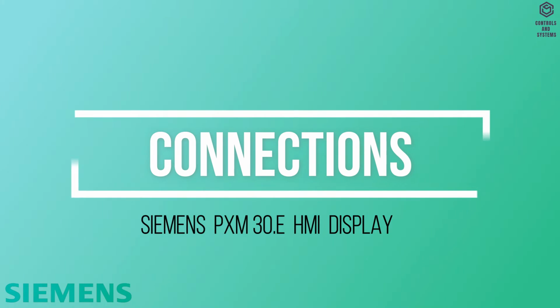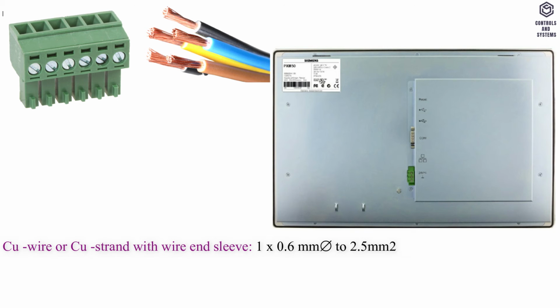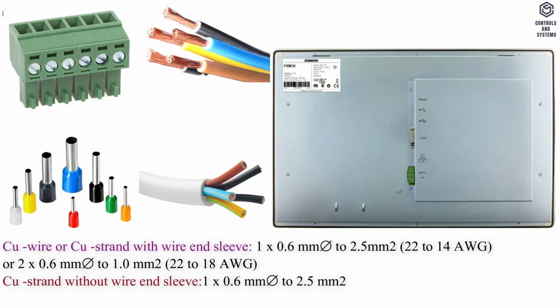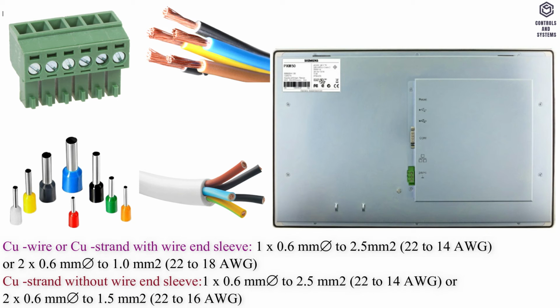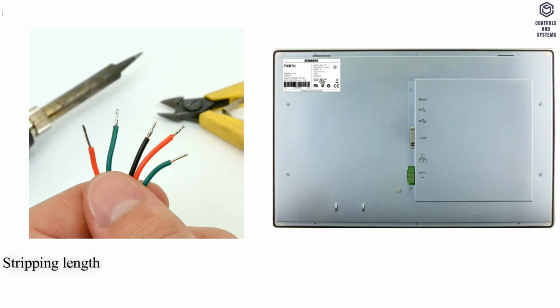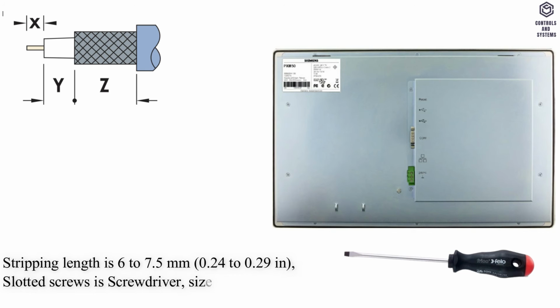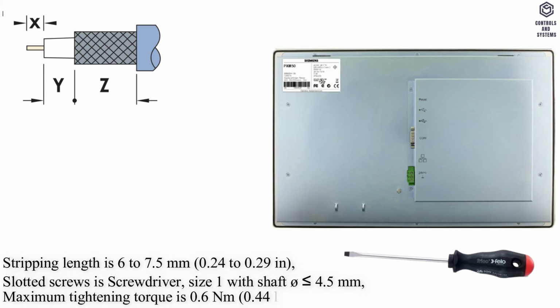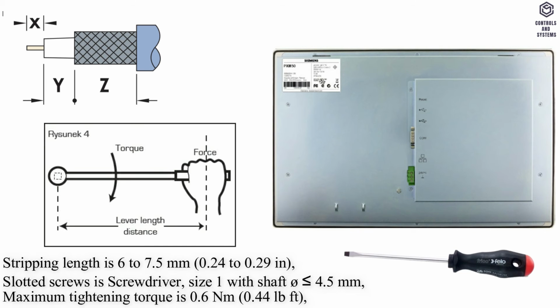Connections. Solid wire or stranded wire with wire end sleeve. Stranded wire without wire end sleeve. Stripping length is 6 to 7.5 mm, 0.24 to 0.29 in. Slotted screws: screwdriver size 1 with shaft diameter less than or equal to 4.5 mm, maximum tightening torque is 0.6 Nm, 0.44 pound-foot. Ethernet interface.